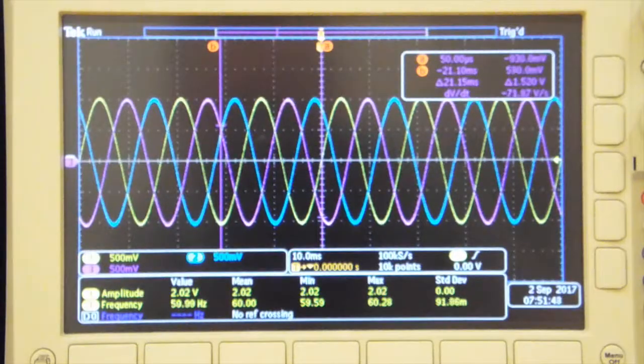The Novatech Instruments Model 409B can also simulate 3-phase power. The 3 outputs are connected at 60 Hz, separated by 120 degrees. This is in phase synchronous operation.